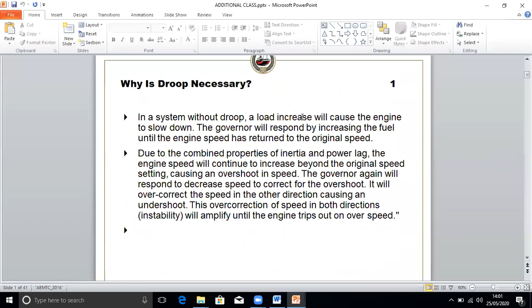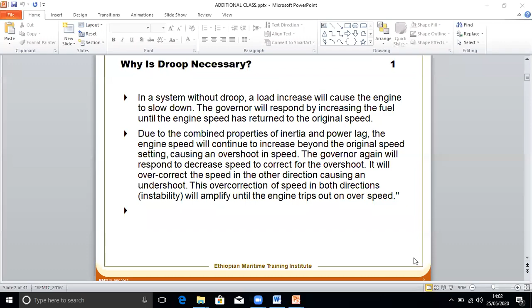Due to the combined properties of inertia and power lag, the engine speed will continue to increase beyond the original speed settings, causing an overshoot in speed. So the governor will again try to respond to decrease in speed to correct the overshoot. It will overcorrect the speed in the other direction, causing an undershoot. So basically this will create an instability, or the engine can trip. So that is why we need a droop.